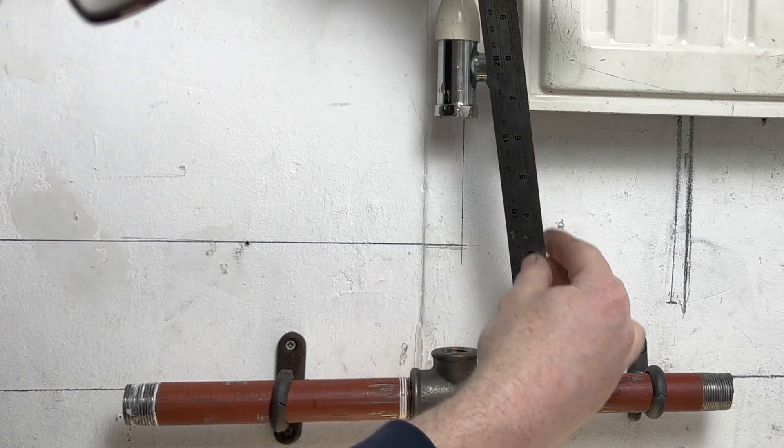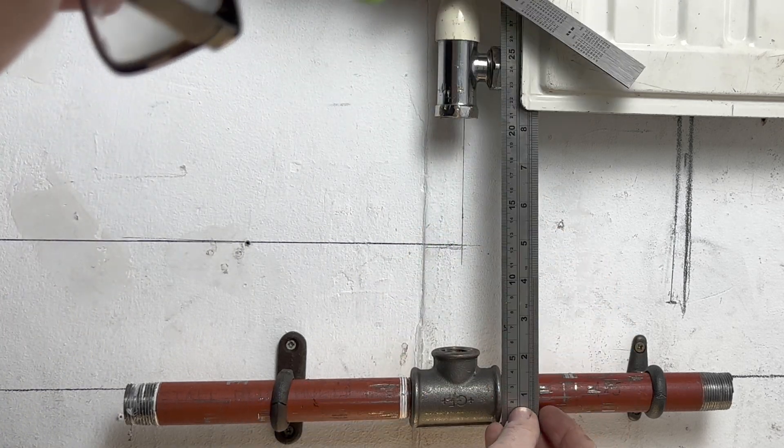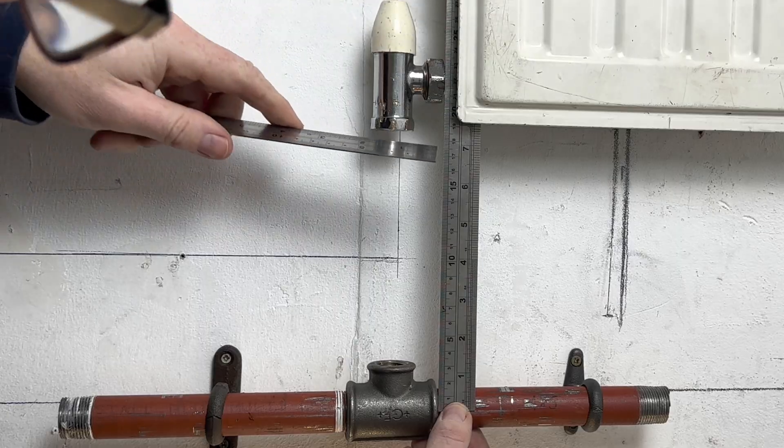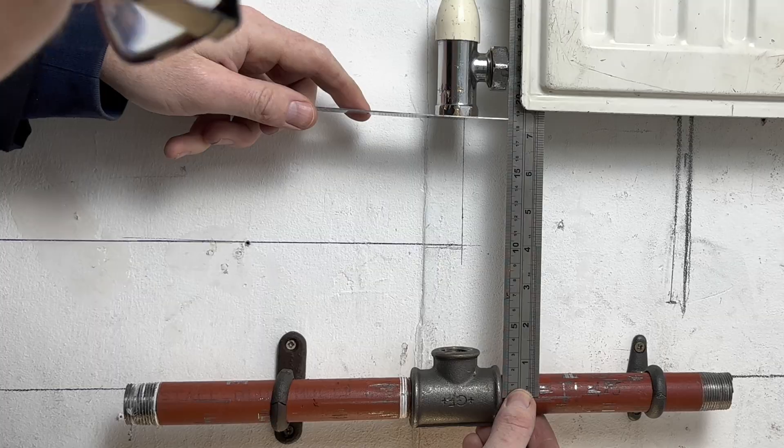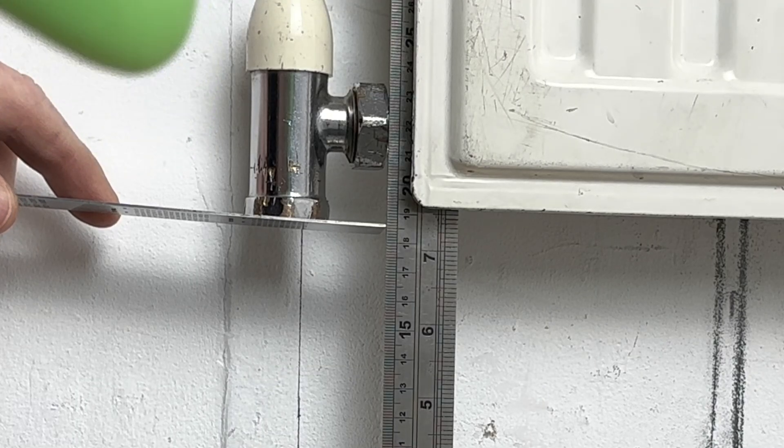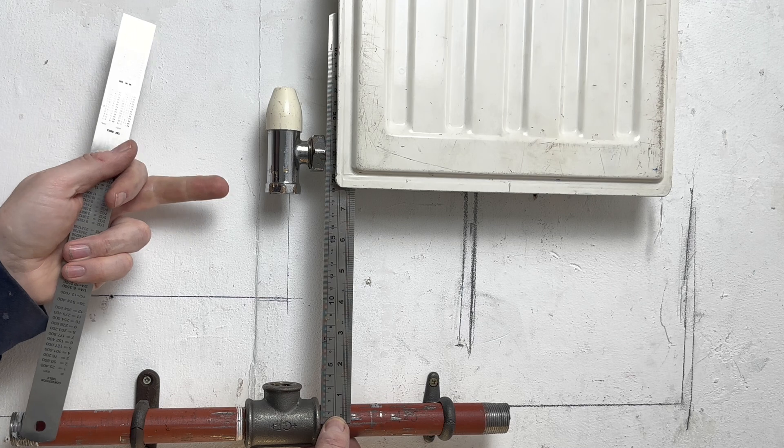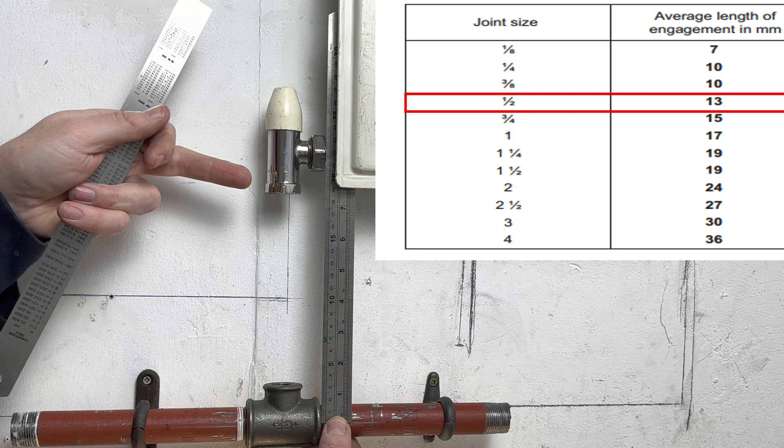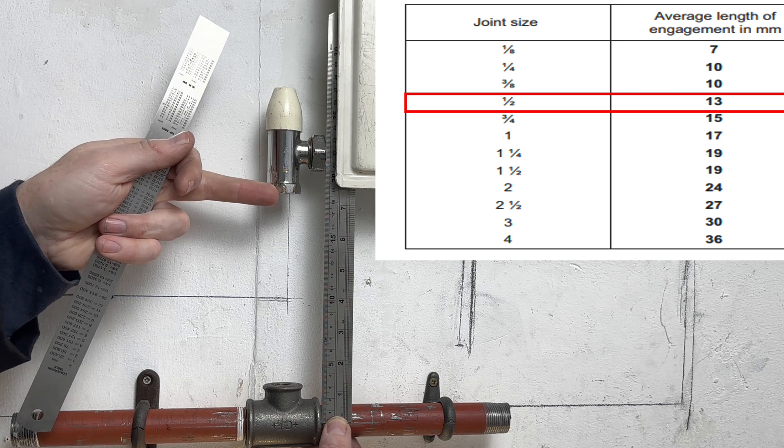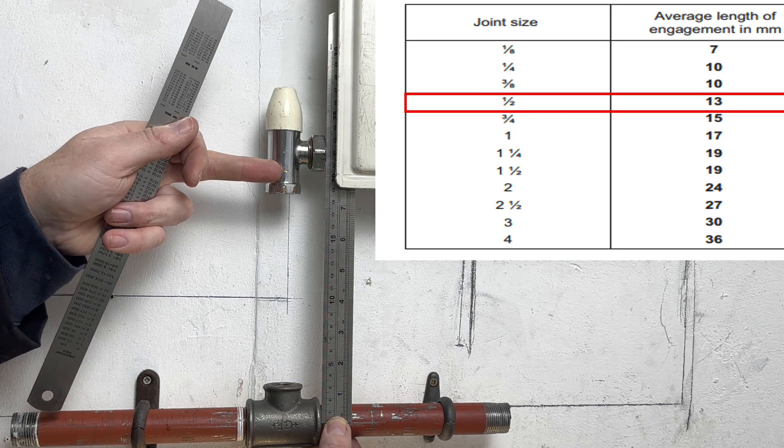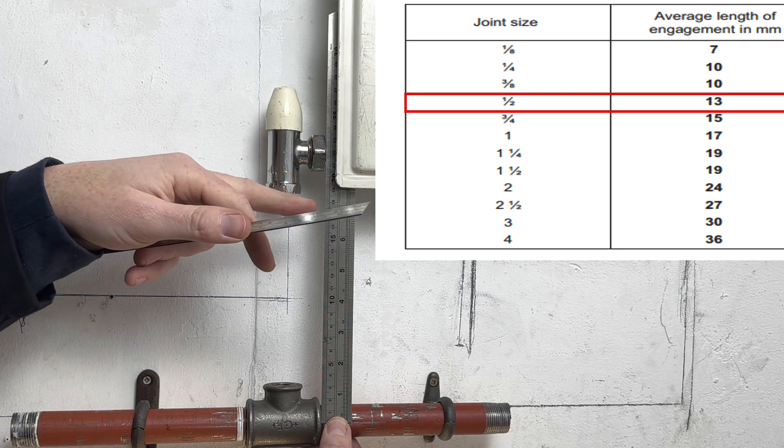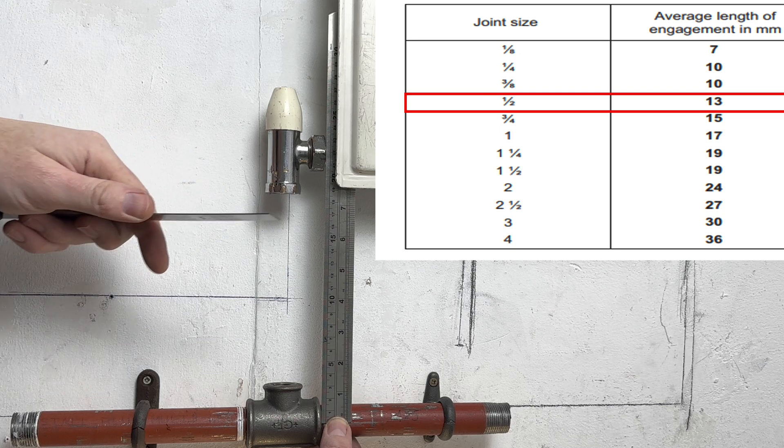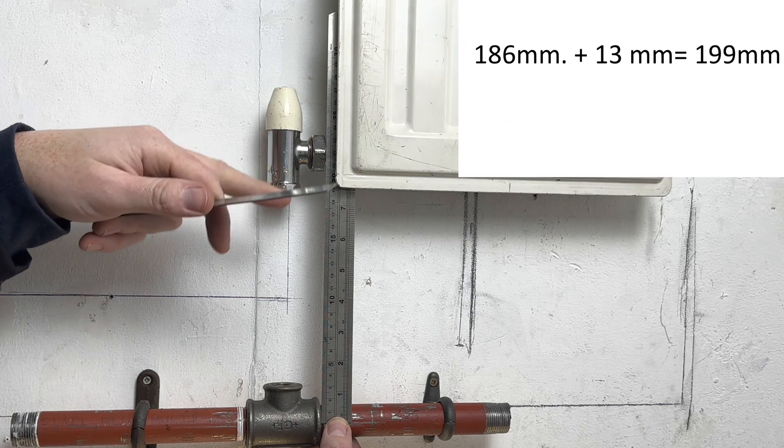So what we do is from the centre of the pipe, we measure to the top. So it's 186mm. Low-carbon steel goes in, half-inch pipe goes in 13mm. So what we then do is 186mm plus 13mm equals 199mm.